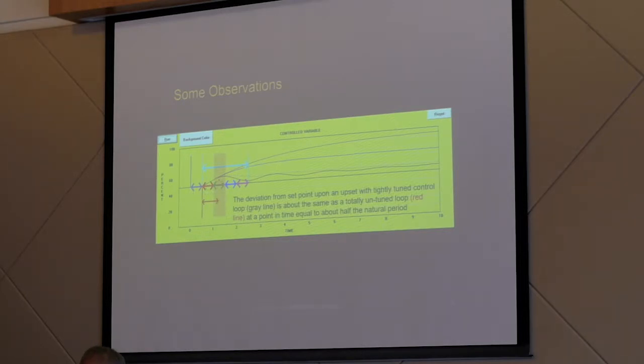Basically, up until you hit about the second apparent dead time, all those processes' reactions are identical. An overtune process, a no control process, in the first half of the natural period, the response is identical. So what that means is, if you're tuning a loop and you're breaking something in less than twice the apparent dead time, you aren't going to fix it with tuning the loop. You got a lag problem, okay?